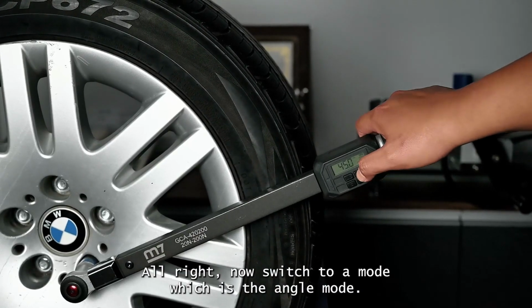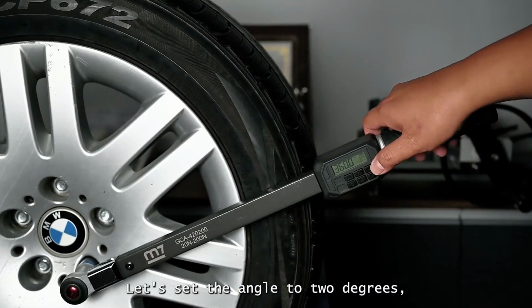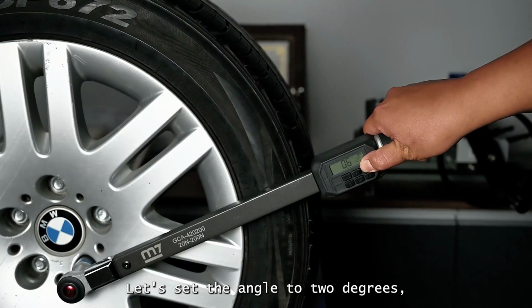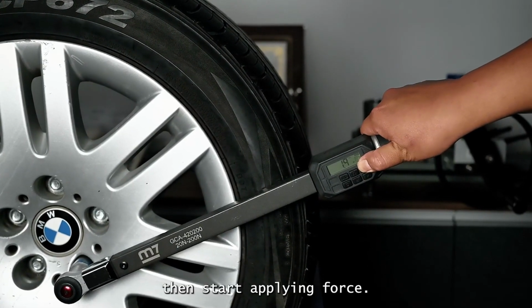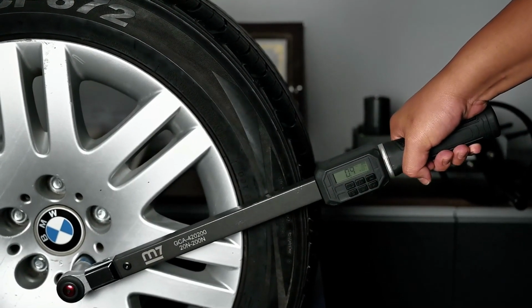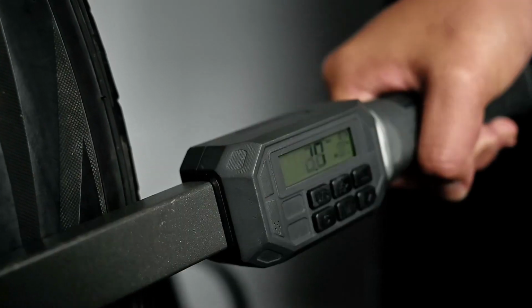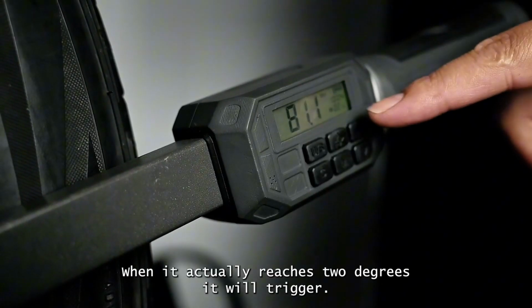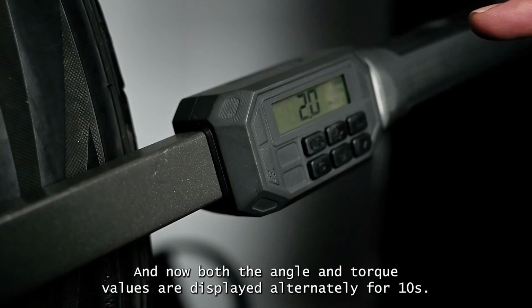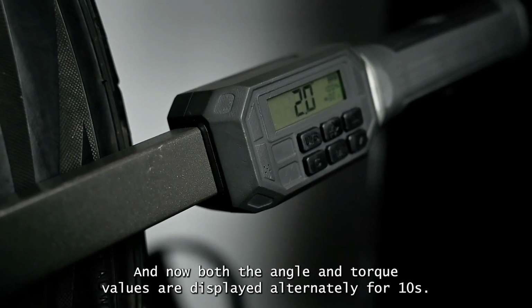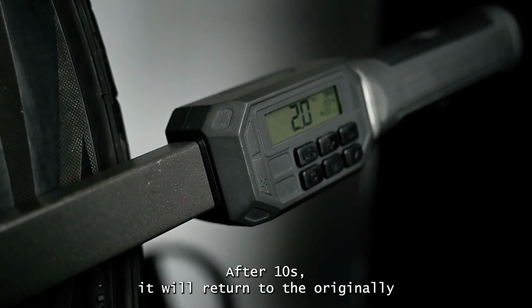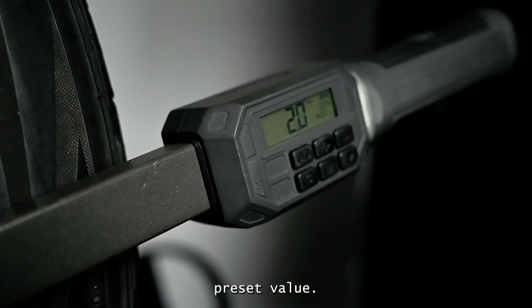Alright, now switch to A mode, which is the angle mode. Let's set the angle to 2 degrees. Then start applying force. Alright, when it actually reaches 2 degrees, it will trigger, and now both the angle and torque values are displayed alternately for 10 seconds. After 10 seconds, it will return to the originally preset value.